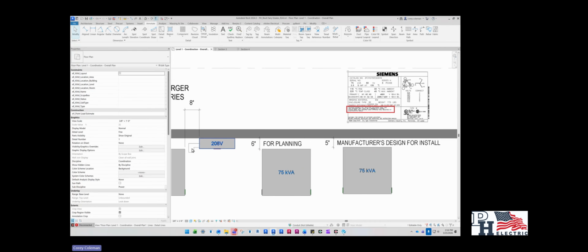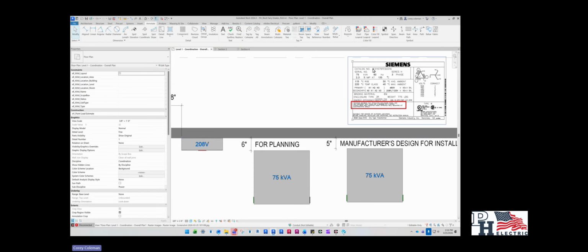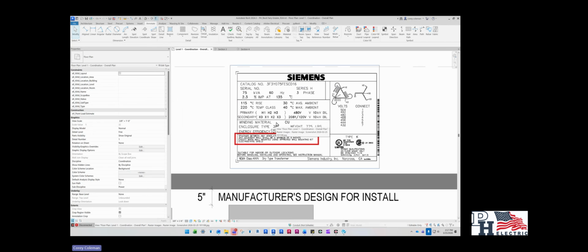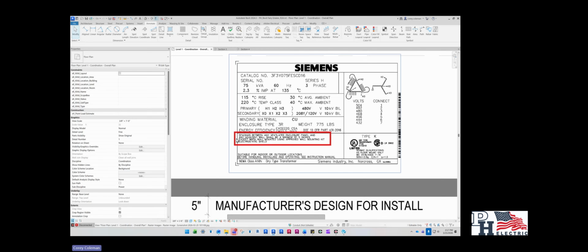When you're laying out your electric rooms and you don't have the specifications for the transformer or don't know the manufacturer specs, you should plan for 6 inches of space behind your transformer. And then when you actually get the specifications or the submittal from the manufacturer, right on the transformer, I would say boilerplate here, it will tell you exactly the spacing that you'll need on that transformer.